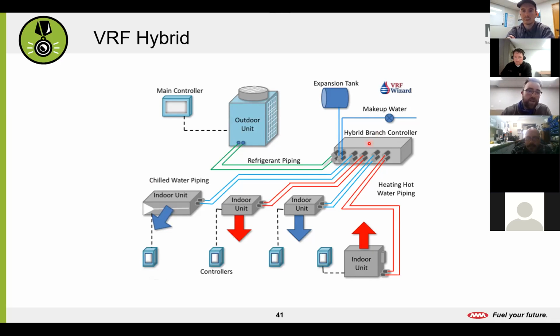This branch box here actually acts as a heat exchanger for a water loop or a water system. So what that means for applications is that instead of having to run copper refrigerant lines to all of your indoor units, instead we're working with water lines. So these blue lines here and these red lines here, these are water lines supplying either heated or cooled water to our indoor unit. And again, the air passes over the coils and gives us either our heating effect or our cooling effect.